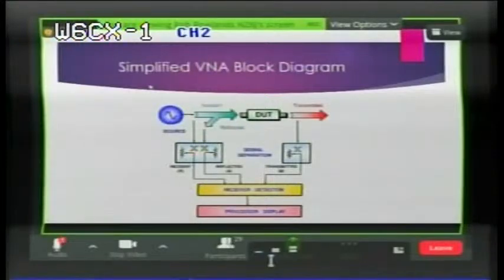A VNA has directional couplers, and I'm not going to go into the minutiae of how directional couplers work. Basically, as I've already mentioned, you have a source, and you send that source in through a directional coupler to your device you're testing. So it's a filter in this case, or a piece of coax. The incident signal is being measured here, and the reflected signal is being measured. The difference between the incident signal and the reflected signal is called return loss. And return loss and SWR are different names for the same thing.